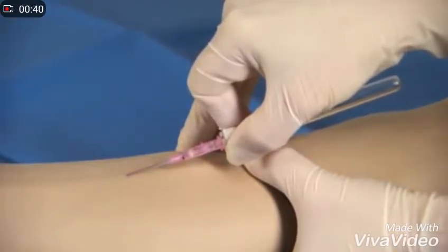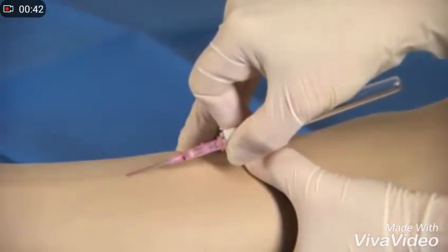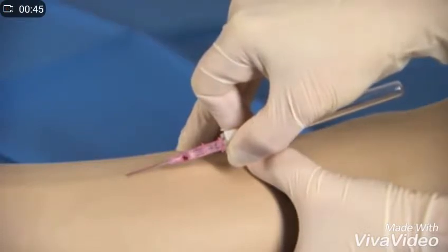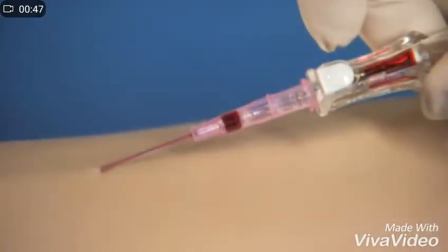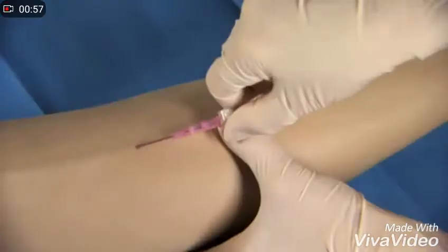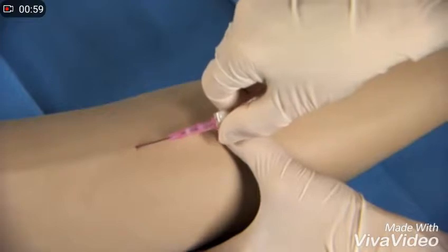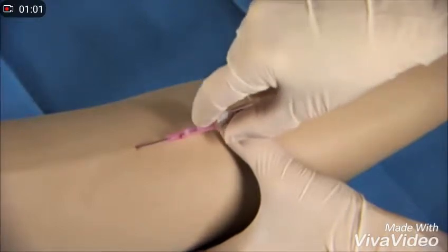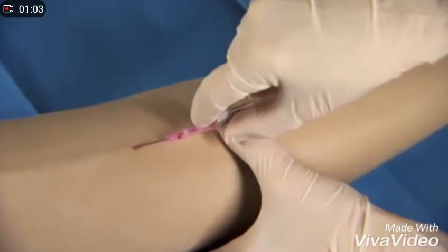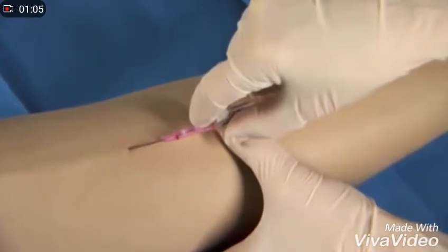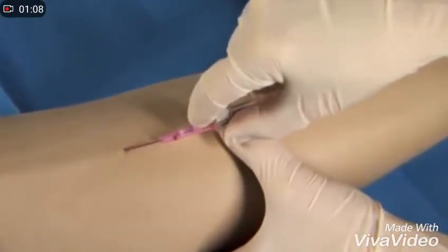Look for initial blood return along the catheter in 20 through 24 gauge catheters, then in the flash chamber behind the white button. In 18 gauge and larger, blood return will be only in the flash chamber. Once you see blood return, lower the catheter angle and advance the entire catheter and needle unit slightly. This ensures the catheter tip, and not just the needle tip, is within the lumen of the vessel.